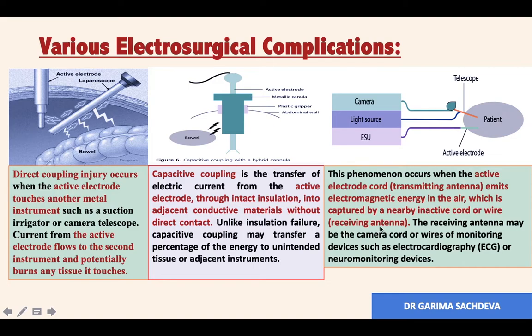The third is antenna coupling. Antenna coupling is when there is an active electrode which emits electromagnetic energy, which is captured by a nearby inactive electrode — could be an ECG lead or a camera telescope — which when it comes in contact with the patient, causes burns.